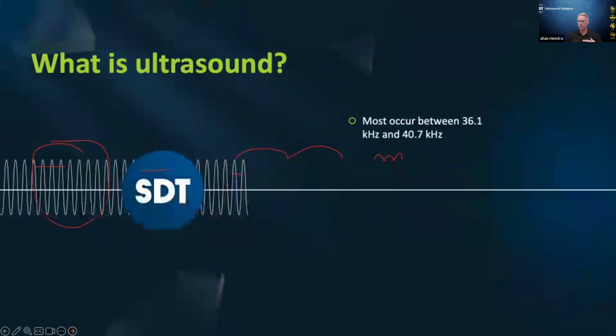Another advantage of ultrasound is directionality. The higher we go in the frequency range, the more directional the signal becomes. And when the signal becomes directional, again, we're not being interfered with by other assets that might be producing ultrasound nearby. So we have distance, we have directionality, and then the third characteristic of sound is its ability to transition from one medium to another, what I term boundary behaviors. That's also a characteristic of high frequency sound which plays to our advantage as inspectors trying to find these sources of airborne ultrasound, which point us towards defects in the asset itself.